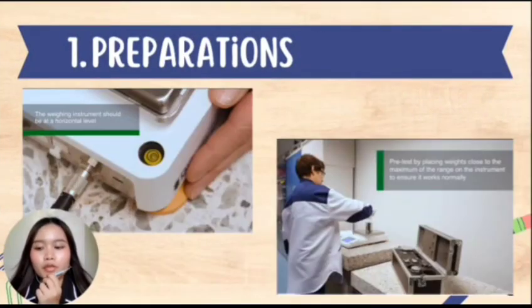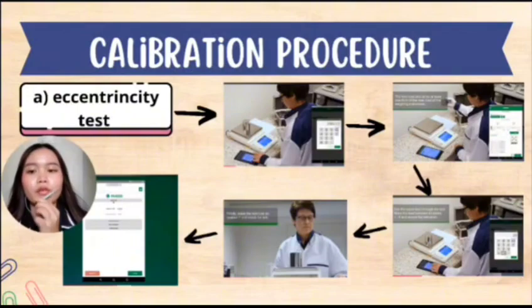Still in preparation, the weighing instrument should be at a horizontal level, and then we should pretest by placing a weight close to the maximum of the range of the instrument to ensure it works normally. Next, we move to the calibration procedure. First, we have the eccentricity test. The eccentricity test is performed to test the effect of the location of the load.